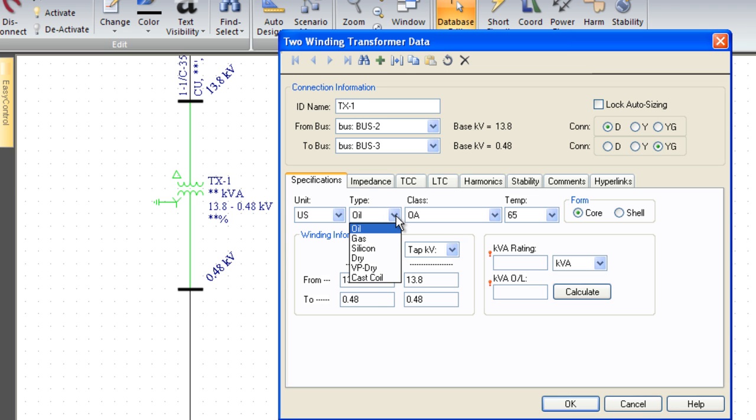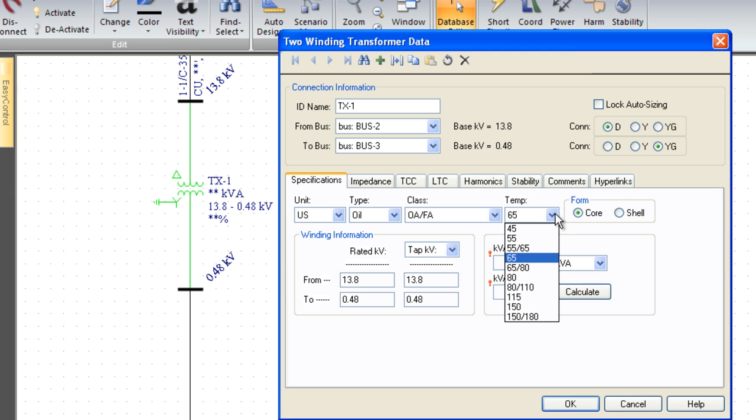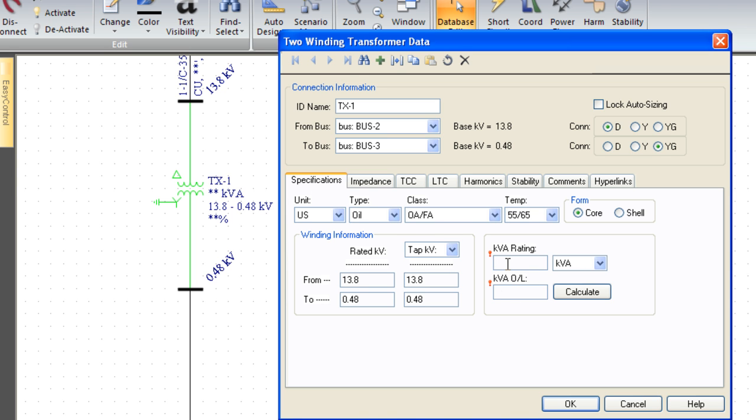The specifications tab describes the information that you would find on the nameplate of that equipment. The type tells us for this transformer whether it's oil, gas, silicone, or dry type. The class rating tells us whether it's OA, forced oil, air, forced air, and things like that. Temperature rise, we'll pick a standard 55-65. Anytime we have mandatory data, we flag the cell in red. In this case we need to know the transformer kVA rating, so I'll type in 1000 kVA.